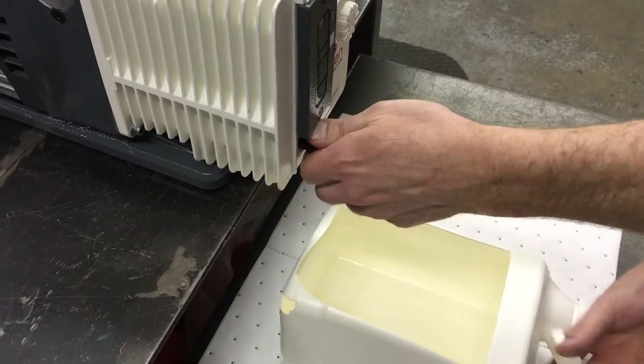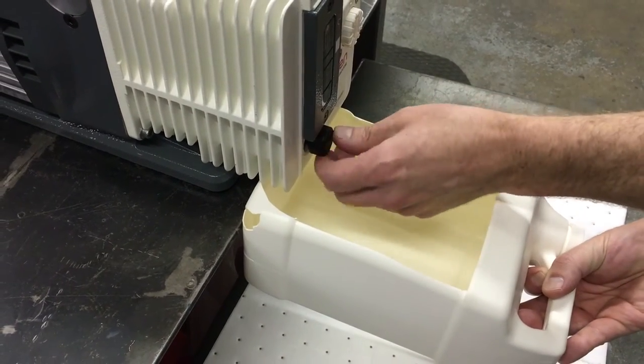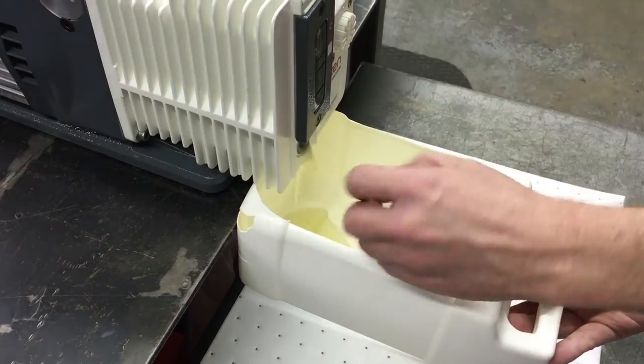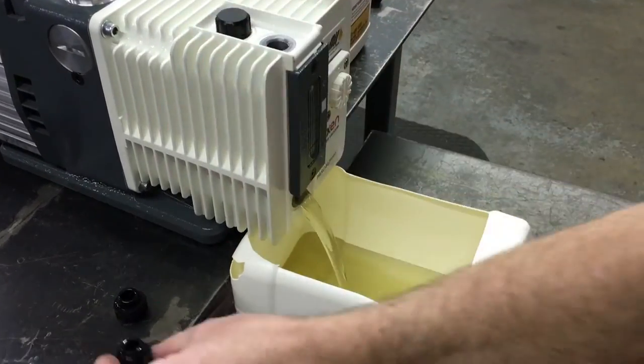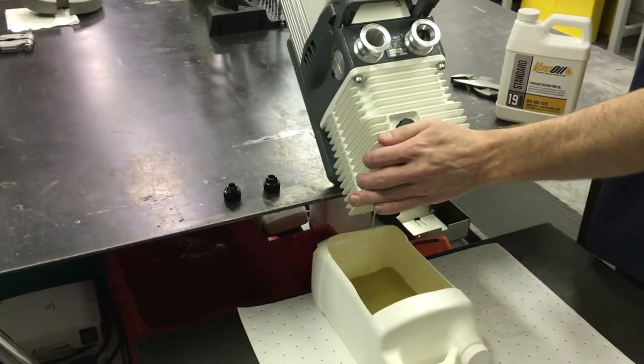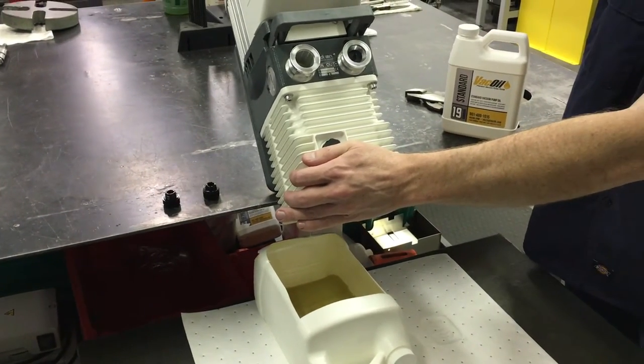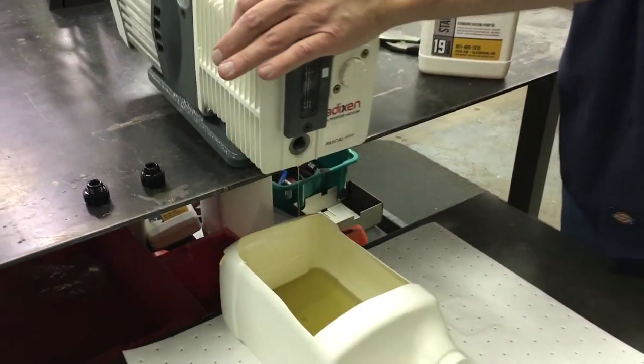To drain the oil use the channel lock wrench to loosen and remove the drain plug. After the drain plug is removed unscrew the oil fill plug for faster draining. Remember to tip the pump to remove as much oil as possible.